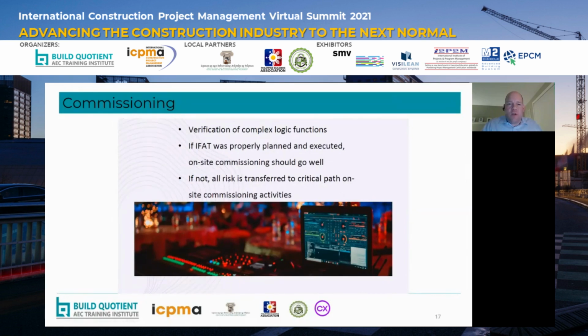If IFAT was done correctly, if it was properly planned and executed, then your on-site commissioning should go well. And that was the whole point of doing all the testing during IFAT, is that by the time we get to this phase of the project during commissioning, we have confidence that these systems are going to work. If IFAT was not done well, then all of the risk that was mitigated during IFAT is instead pushed to this on-site commissioning phase. And that's the critical point here, is that's deferring risk way too late in the project for today's complex systems. For these automation systems, you can't be combining the hardware and the software this late in the game, because instead of actually commissioning, essentially what you're still doing is just debugging the software.